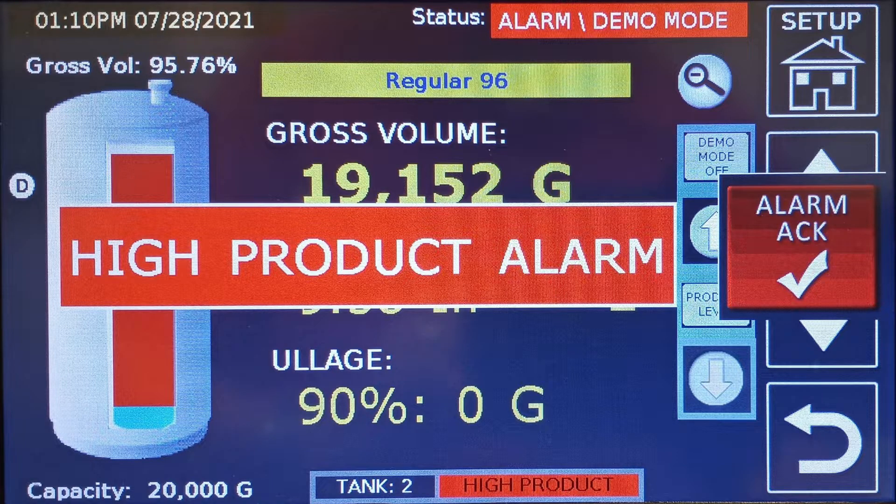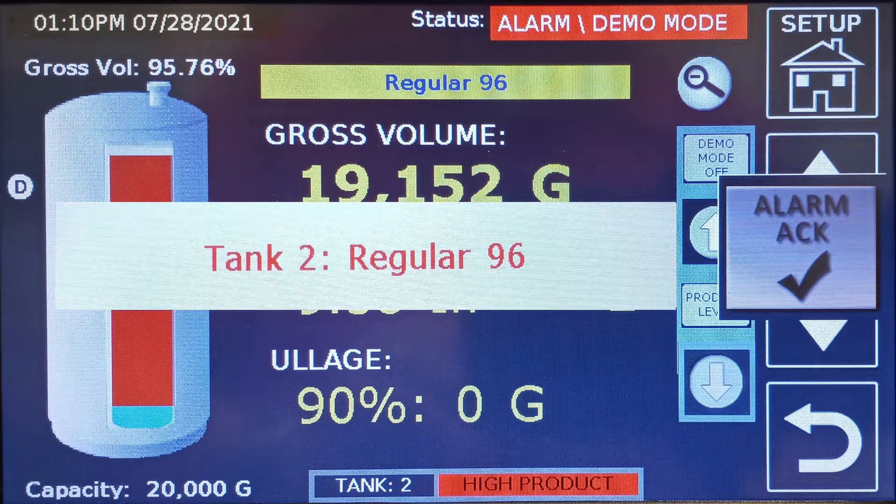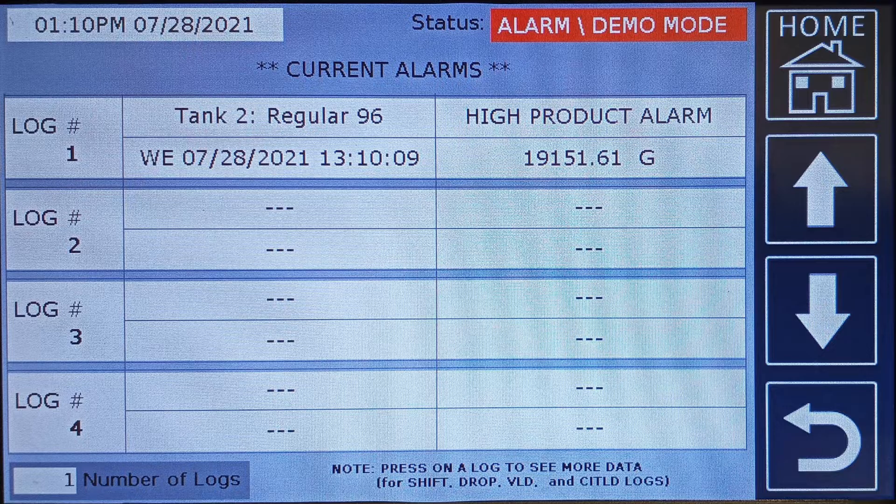The controller horn will sound until the alarm acknowledge button is pressed. The system will alternately switch between the alarm message and alarm location. The remote enunciator will alarm. You can press the acknowledge test switch to silence the remote horn. The alarm light will remain lit. Pressing the alarm acknowledge button will switch to the current alarm screen and it shows the active alarm condition. This alarm will remain active if demo mode is enabled until the level is reduced below the alarm point.